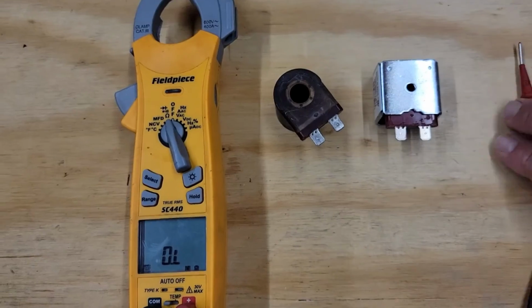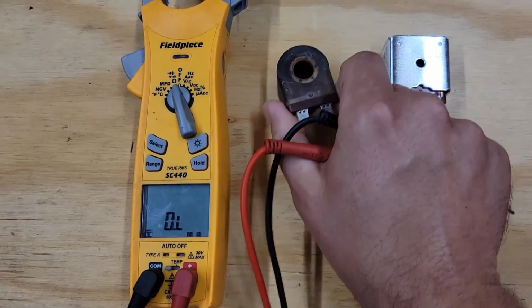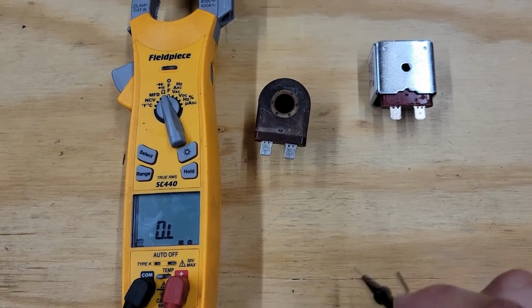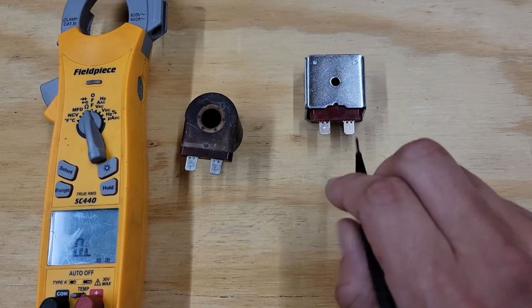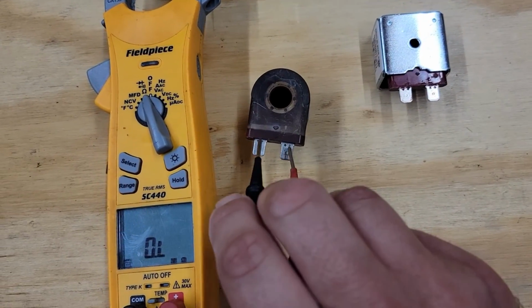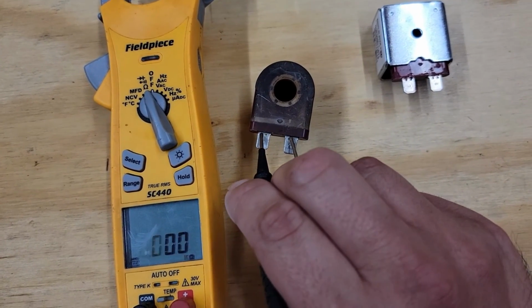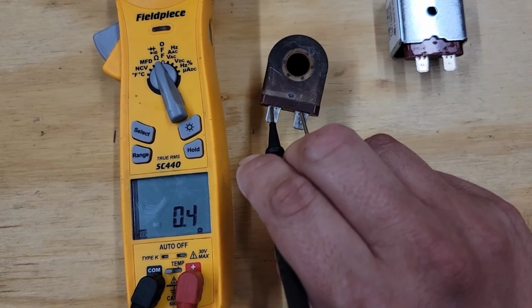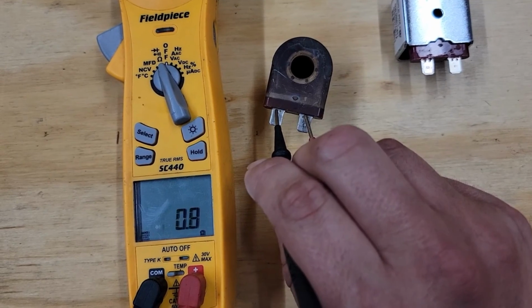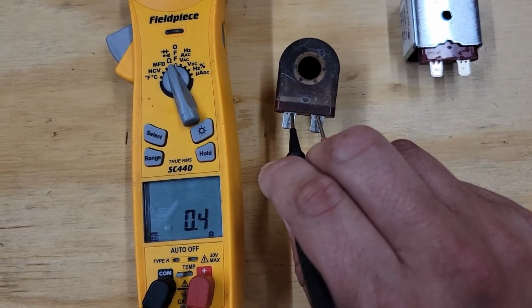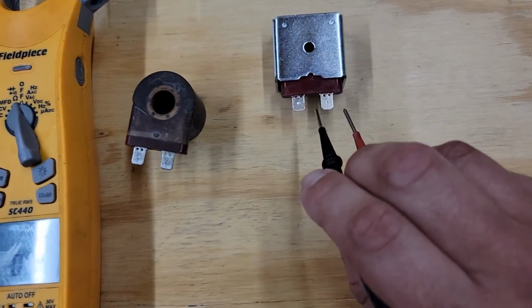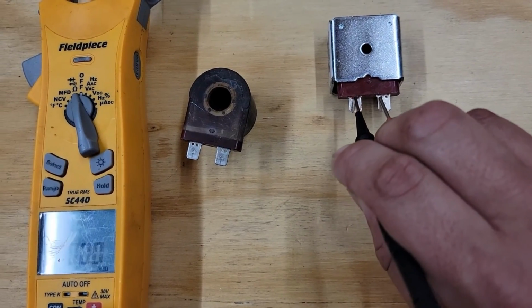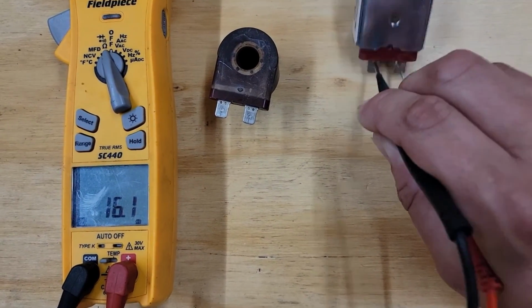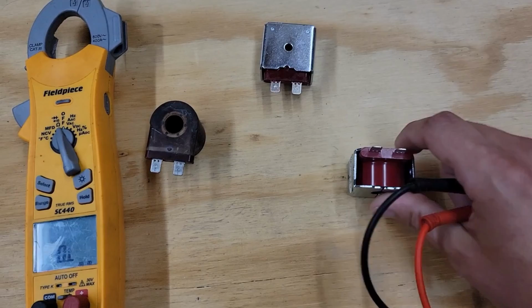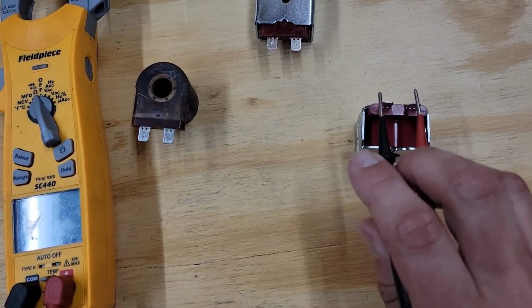Thanks for watching. Right now I'm going to show you the resistance readings of the old bad reversing valve coil that we're replacing and the new reversing valve coil. I'm going to show you the difference. There's definitely a difference. So you can tell it's bad from the reading. What is it? Come on, stay still here. 0.4. All right, now what we should have is around 16. So 16. Now I also have another reversing valve coil that's good.